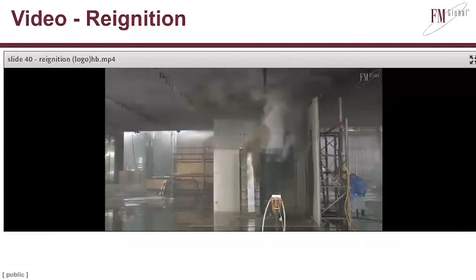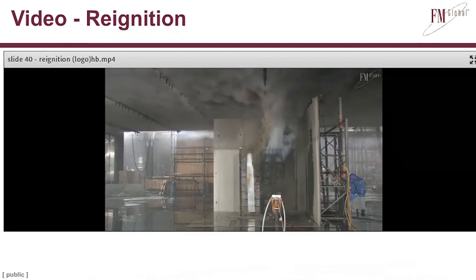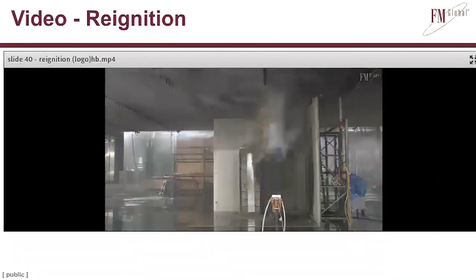But what was more concerning was on the left, in our target rack. We saw little sparks going here and there. And given that thermal runaway could be a slow process, this was most likely happening during the initial fire. It's just that there's not a lot of line of sight, so we weren't really able to see it. But eventually, we had a fully developed fire that had a magnitude very similar to what the initial fire on the main rack looked like. So this shows that the fire can in fact spread for the NMC system from one rack to the next, but it was significantly delayed.